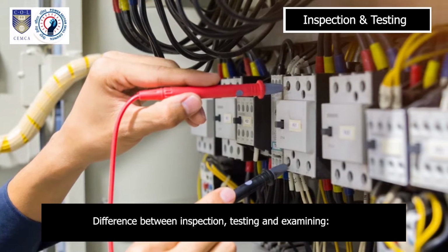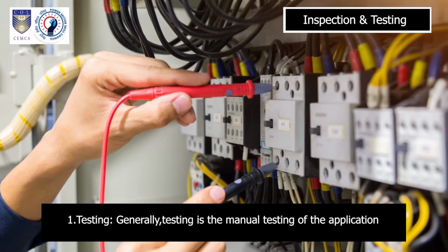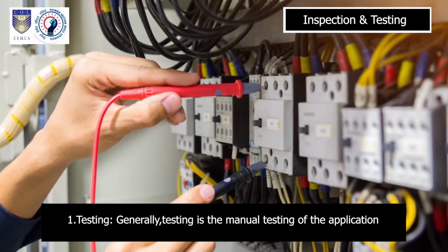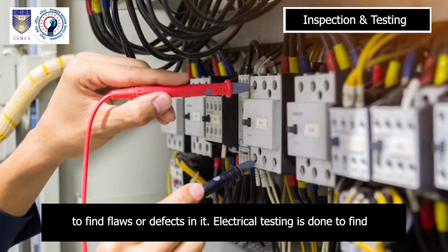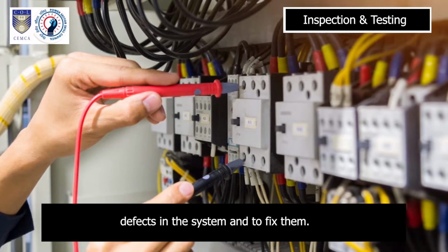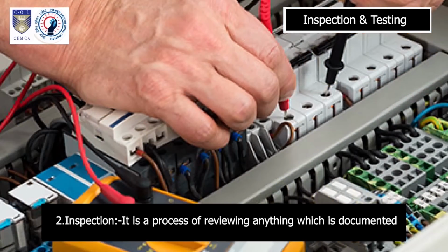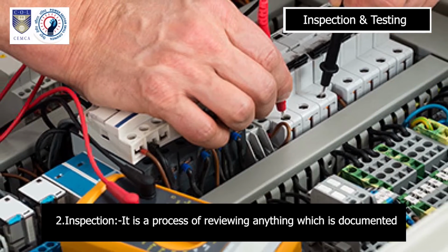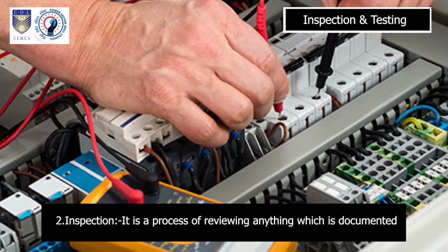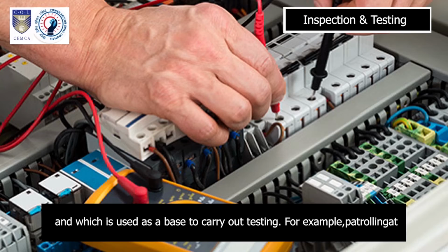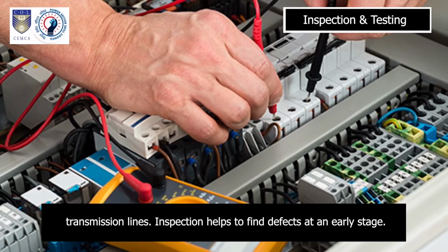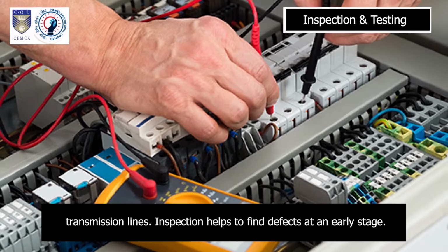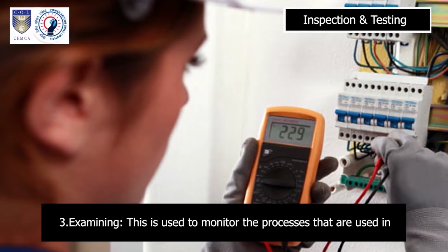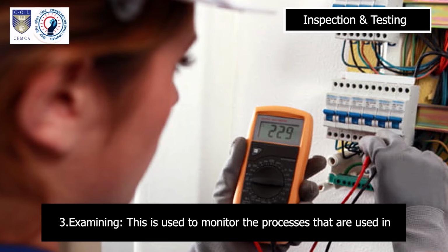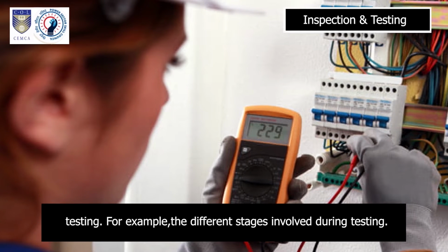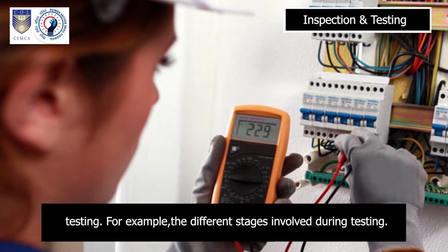Difference between inspection, testing, and examining. 1. Testing. Generally, testing is the manual testing of the application to find flaws or defects in it. Electrical testing is done to find defects in the system and to fix them. 2. Inspection. It is a process of reviewing anything which is documented and which is used as a base to carry out testing, for example, patrolling at transmission lines. Inspection helps to find defects at an early age. 3. Examining. This is used to monitor the processes that are used in testing, for example, the different stages involved during testing.